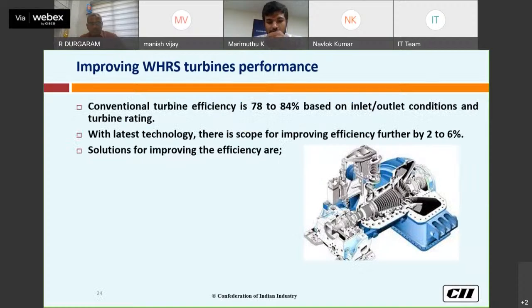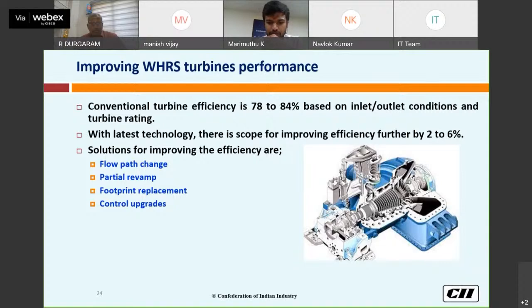So conventional turbine efficiency is around 78 to 84 based on inlet and outlet conditions. With the latest technology, there is scope for improving the efficiency, either by flow path change, partial revamping, or footprint replacement, or with a control upgrade. So this 2 to 6% efficiency improvement is possible in the existing turbines.